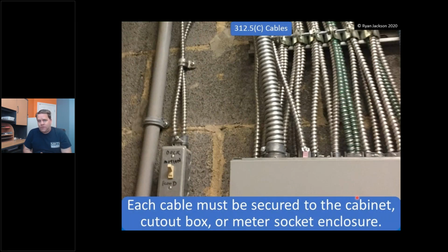So 312.5(C) is what we're going to be talking about today. It's a very misunderstood section. The general requirement is easy enough, but the exception is very misunderstood and very misapplied. So let's make sure we're in the right article. Article 312 covers cabinets, meter socket enclosures, and cutout boxes.